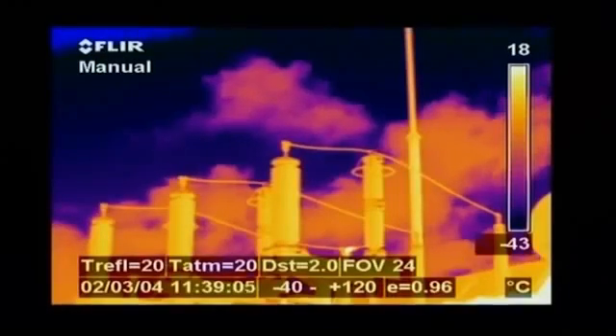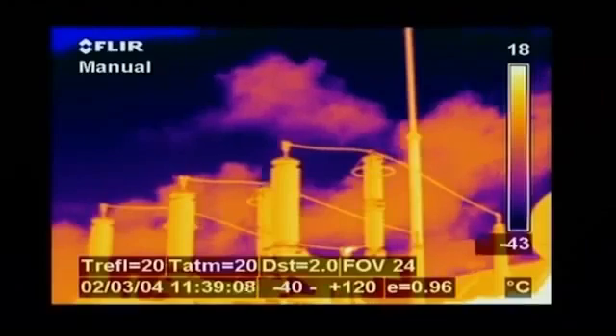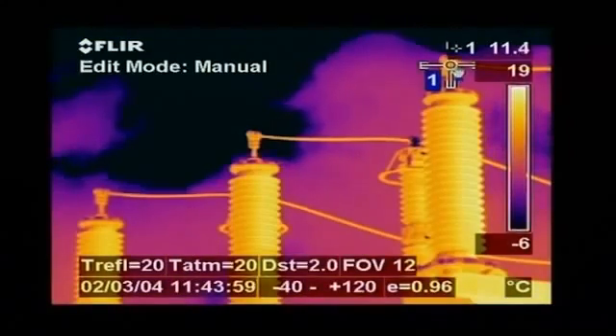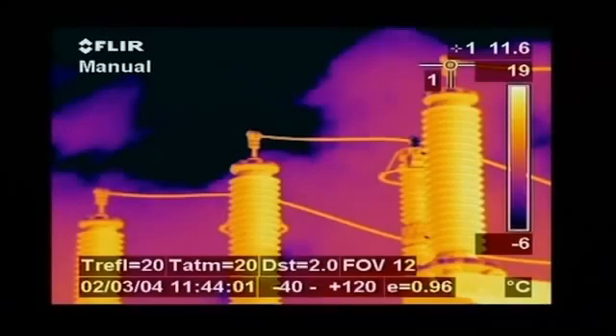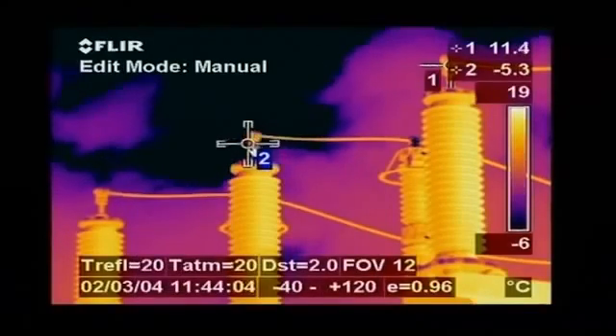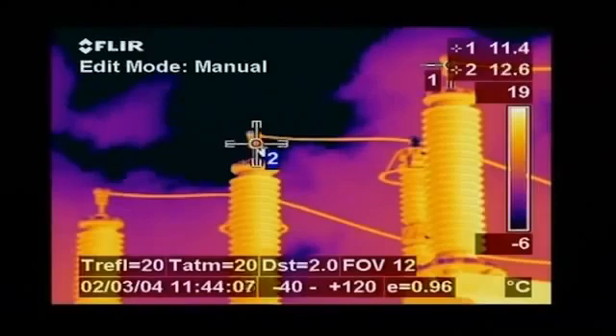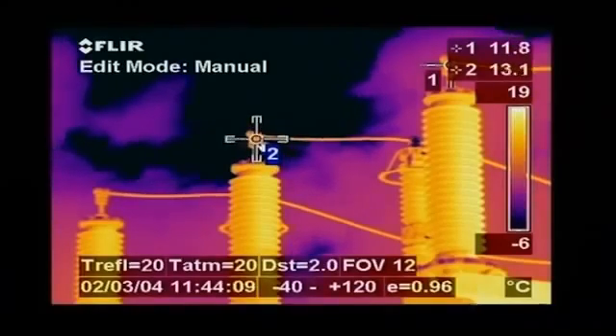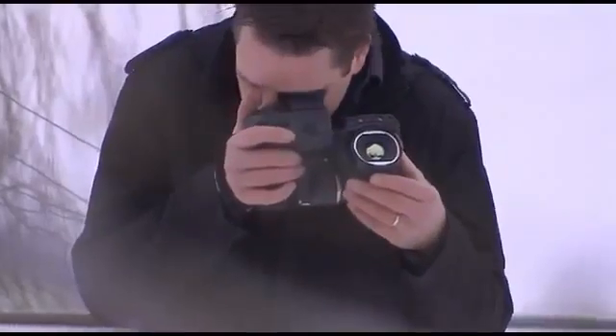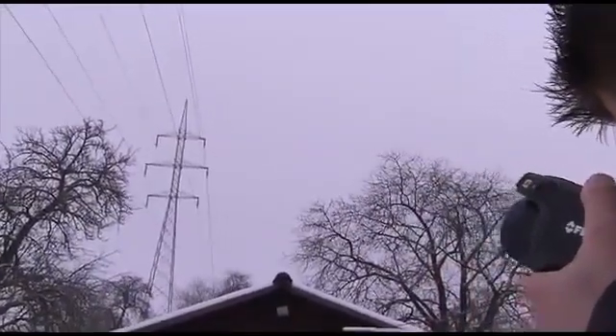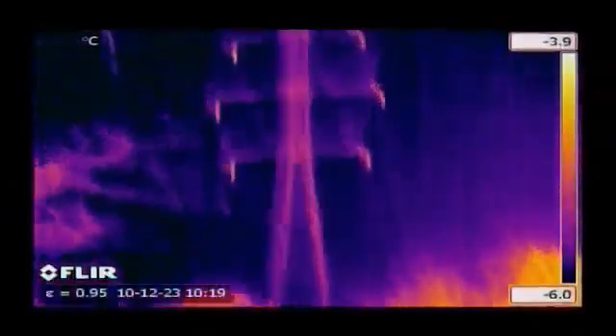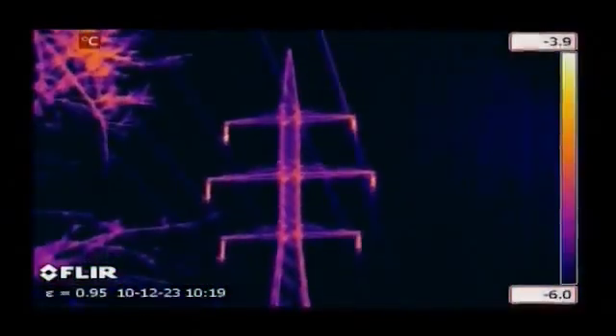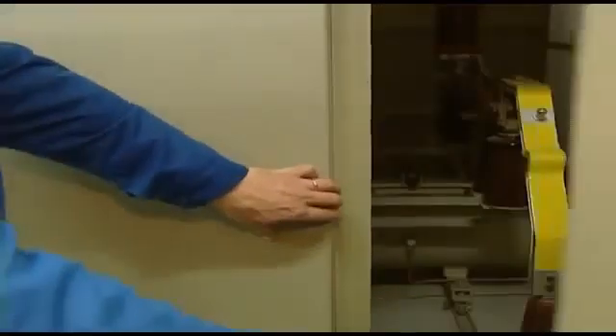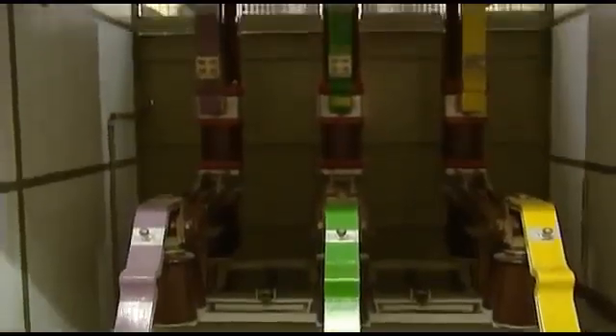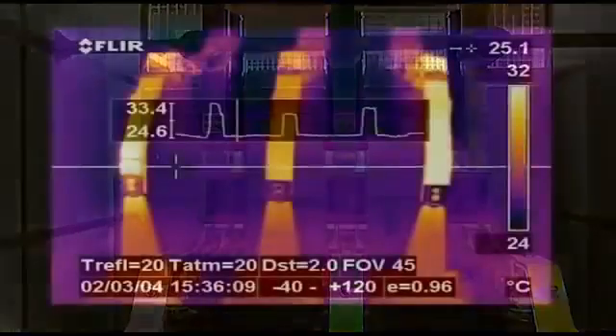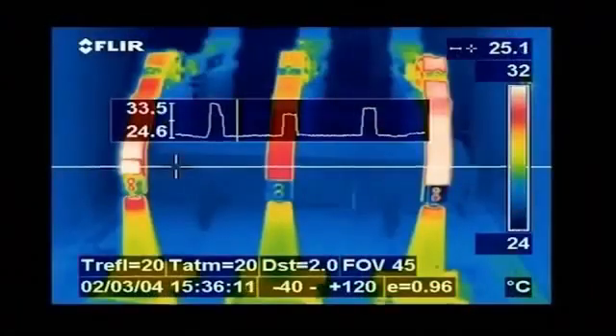Power transformers are often checked with thermal imaging cameras. Temperatures of the cooling fins and the high voltage connections can be compared so that, if necessary, corrective action can be taken before real problems occur. Also, high voltage power lines can be inspected with a thermal imaging camera. Other high voltage installations that are checked with a thermal imaging camera include circuit breakers and switches. Potential problem areas will clearly be shown on the thermal image.